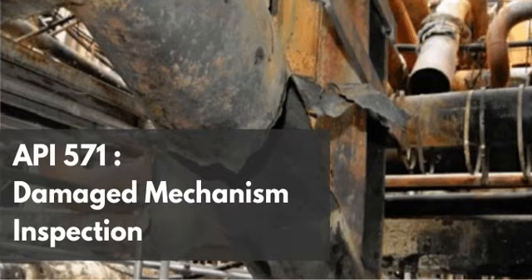And when they do deploy non-destructive examination, NDE, to physically check the tubes, what are the tools? The API protocols specify visual testing, or VT, to spot distinct bluish corrosion products on the copper, right? Yes. The interaction between the copper alloy and the ammonia often leaves behind complex cuprammonium ions, which present as a very visible, unnatural bluish scale on the surface. So if an inspector sees that blue tint near a tube sheet, they know ammonia attack is happening. Right. It's a huge red flag. But the visual cue isn't the crack itself.